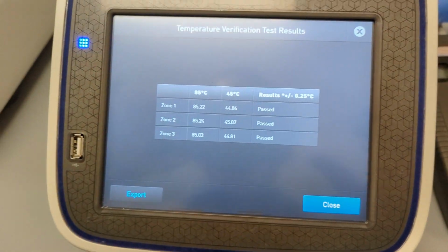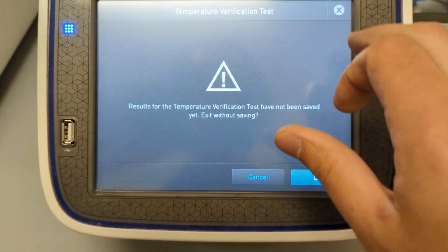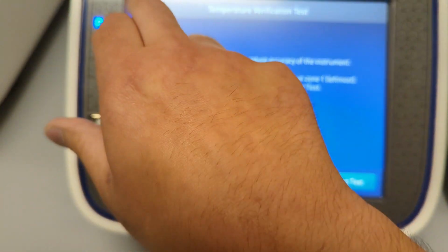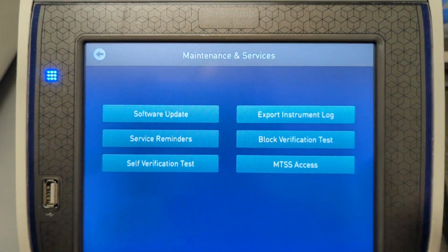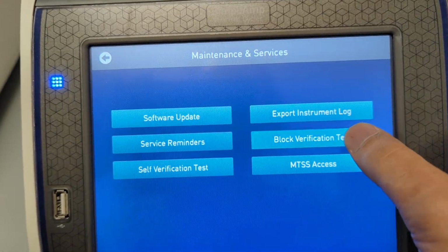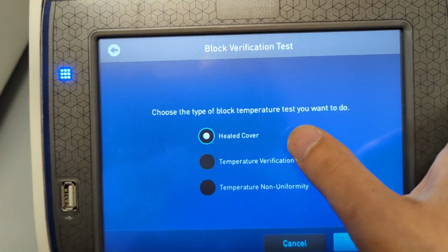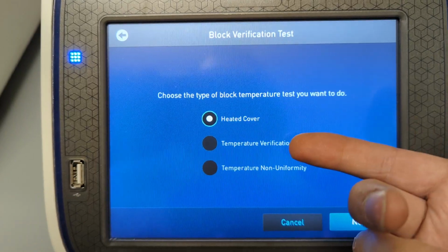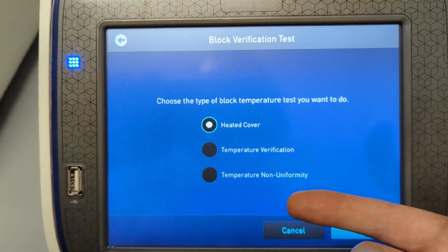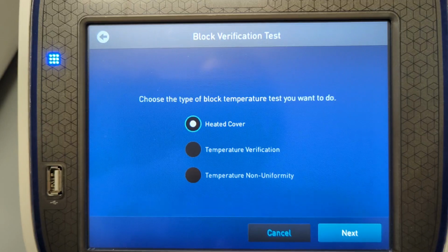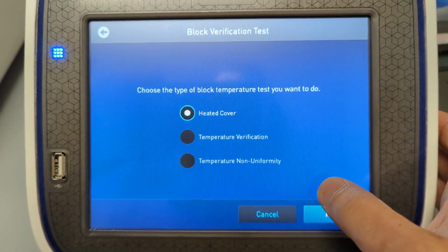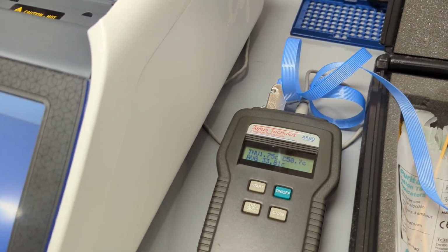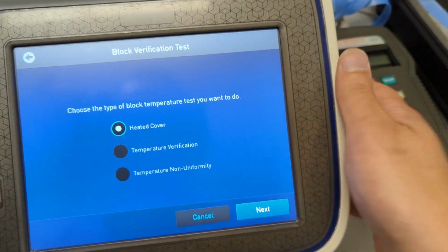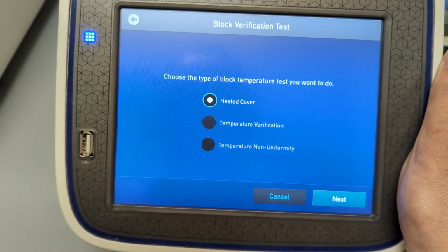But anyway, that's what you need to do these calibrations, and I can kind of show you where you can access that. If you go back to maintenance and services, on the interface you go to block verification test, verify block temperature. There's the heated cover test, temperature verification, and then next I'll do temperature non-uniformity, not in this video. That should pass fine though. And you need to hook this guy up to the RS-232 port in the back. But yeah, that's just a brief rundown on how to do a calibration verification on these.